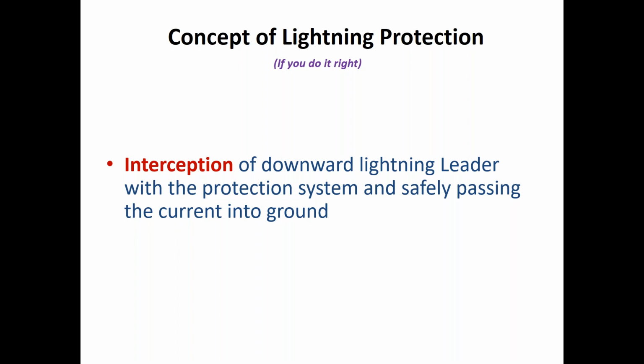I repeat: if you do it right, the concept of lightning protection is that whenever there is a downward lightning flash, which we call the step leader, and when it is around 50 to 100 meters away, we implement a lightning protection system on the structure that will send a streamer to intercept the step leader. It actually invites the lightning to that particular system, which we call the lightning protection system, and safely passes the lightning current to ground.